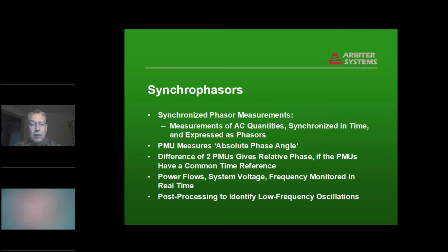Synchrophasors you're probably becoming familiar with or heard of at least. They're basically measurements of AC quantities on the power system, and they're synchronized in time so that basically every PMU that's out there is running on the same time scale, and their sampling is even synchronized to each other in effect. And we express those as phasors. And the PMU, what it does is measure absolute phase angle. It measures the phase angle at the location of the measurement relative to a standard cosine wave that's synchronized to the top of second. And that isn't all that useful in and of itself, but what it's useful for is by looking at the difference between two PMUs' measurements, and that gives the relative phase between the substations or the feeders or whatever, as long as the PMUs have a common time reference. So that's why we use the precision time for PMUs.